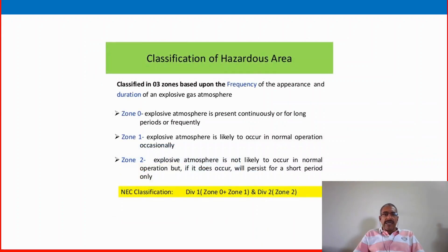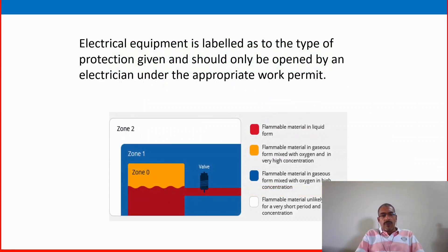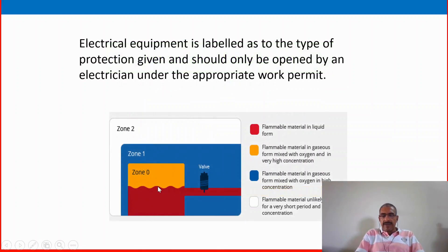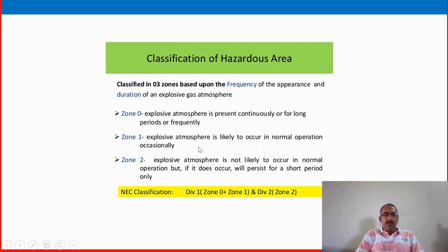Classification of hazardous areas: classified in 3 zones based upon the frequency of appearance and duration of an explosive gas atmosphere. Zone 0 — explosive atmosphere is present continuously for long periods. In Zone 0, explosive atmosphere is continuously available. Zone 1 — explosive atmosphere is likely to occur in normal operation or occasionally.